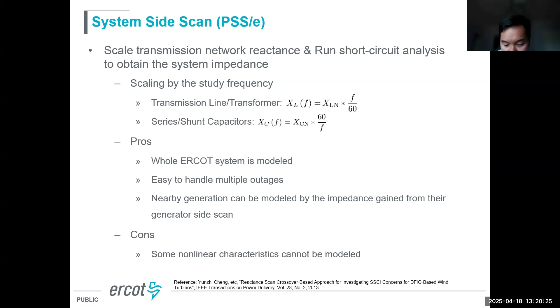The main idea is to scale the impedance of the transmission line, transformer, series capacitor and shunt capacitor. And this is the formula we use to scale the impedance of the lines, transformers, and capacitors. After that, we can run the short circuit analysis to obtain the system impedance. It's very straightforward, but you need the Python script to do it. And we have a tool to run the frequency scan, and we have used this one for hundreds of SSR studies.